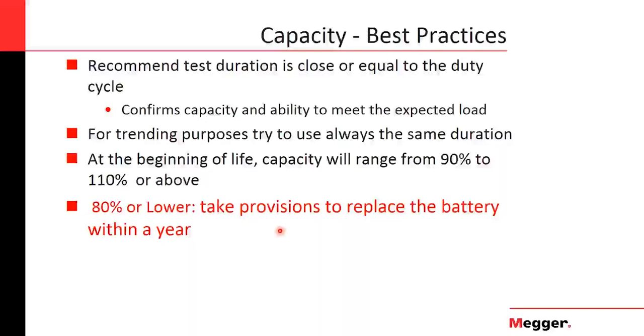It's one cycle that you're taking out of the battery, but mainly because of what it represents, the battery has to be offline. You should not be drawing additional current from the battery, or you need to account for that if you're doing an online test. And the most preferred method is to bring a backup system, a trailer with a battery in it, just to have peace of mind with the substation and not risk an additional fault in the system.